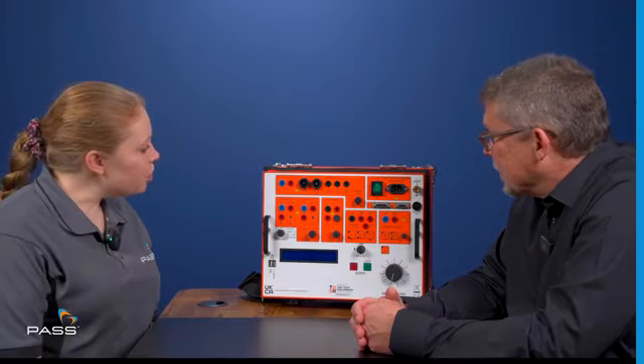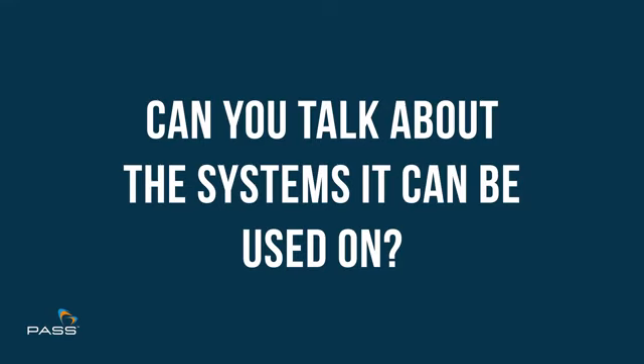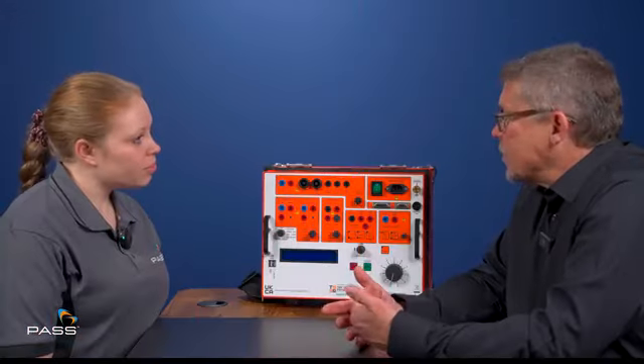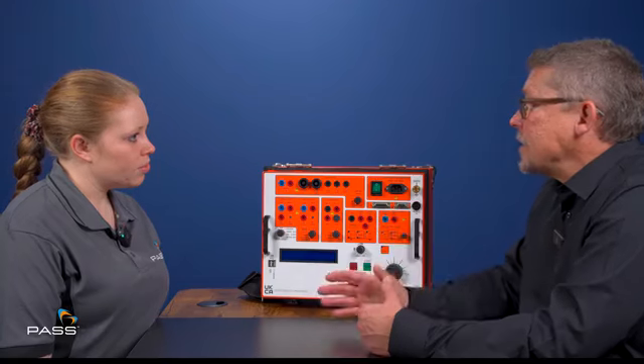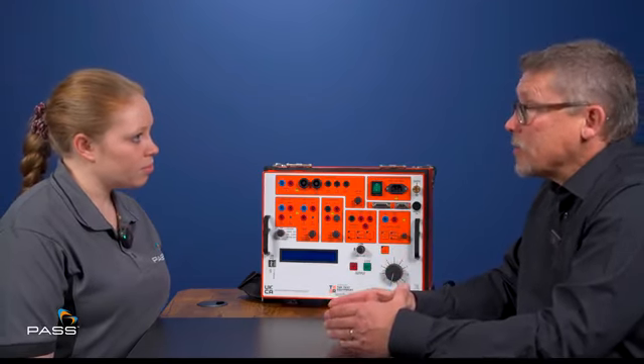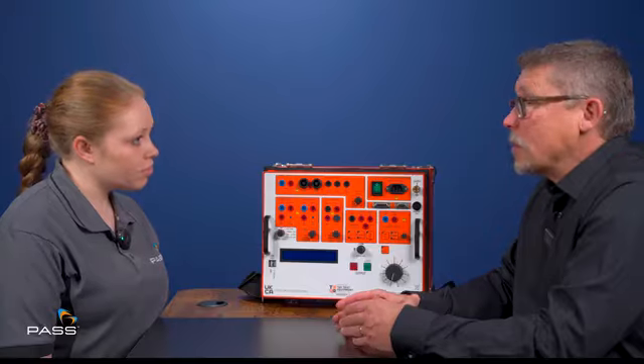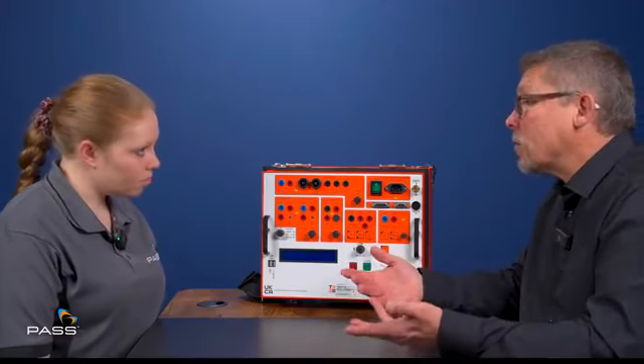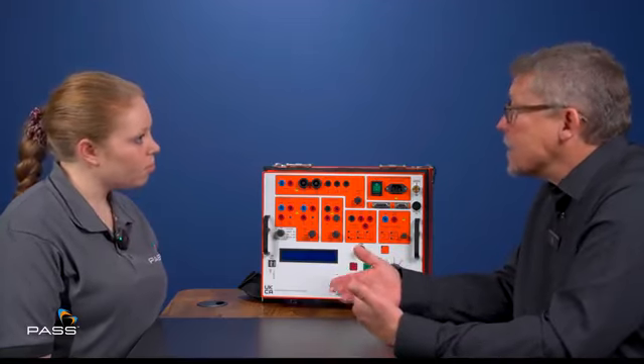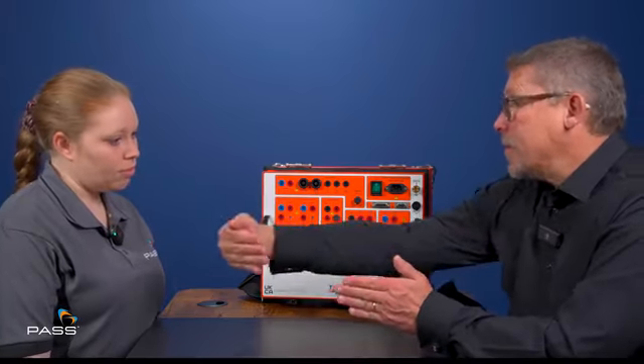So could you tell me a bit about the systems it can be used on, please? Yeah, so effectively what you're using this for is to test infrastructure around plant that's expensive. So, for example, you install an offshore wind farm. The actual windmills themselves, they're expensive. They will be then fed into transformers. They're expensive. So this unit, you'd be using that to test the relays that protect that infrastructure from overcurrent, undercurrent, running the wrong way. For example, some relays are designed that they'll allow current to go that way, but not that way.